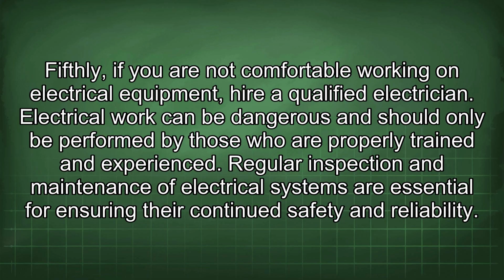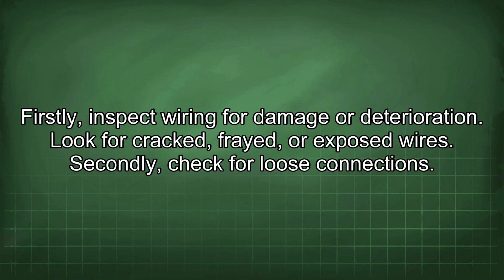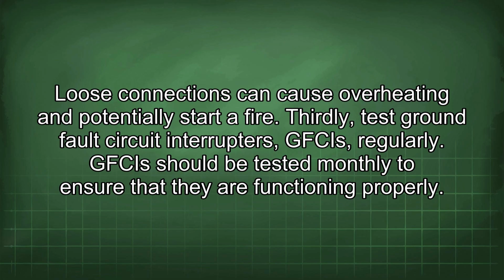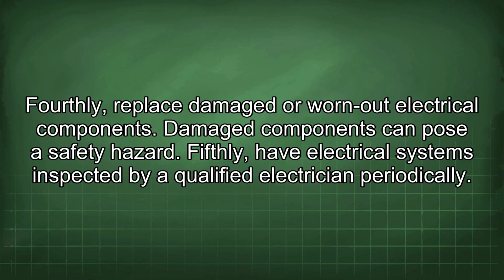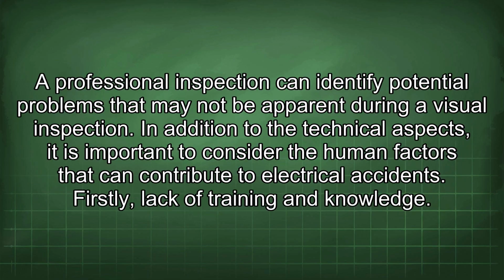Regular inspection and maintenance of electrical systems are essential for ensuring their continued safety and reliability. Firstly, inspect wiring for damage or deterioration. Look for cracked, frayed, or exposed wires. Secondly, check for loose connections. Loose connections can cause overheating and potentially start a fire. Thirdly, test ground fault circuit interrupters, GFCIs, regularly. GFCIs should be tested monthly to ensure that they are functioning properly. Fourthly, replace damaged or worn out electrical components. Damaged components can pose a safety hazard. Fifthly, have electrical systems inspected by a qualified electrician periodically. A professional inspection can identify potential problems that may not be apparent during a visual inspection.